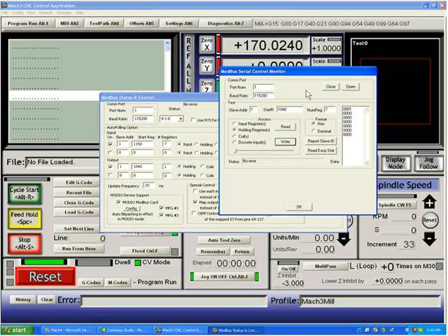For example, if you had a DL5 and it has an LED on bit 3, you could come into this device, put in a 4 hex, hit write, and the LED on the Modbus device would then light up. So the Modbus test dialog is very important to you when you're trying to set up an unknown Modbus device.